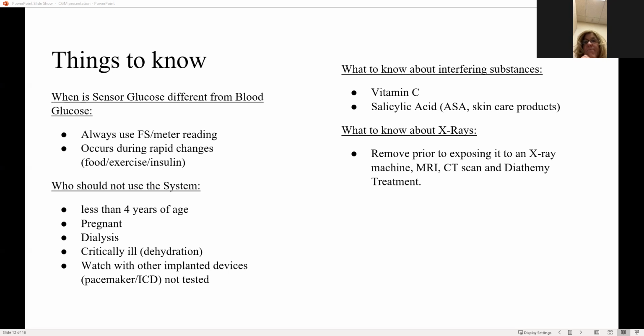X-rays, MRIs, CT scans, and diathermy, which is the use of heat. Any of those types of situations will likely ruin your Libre monitor, and it will not prove accurate after it's been scanned or has gone through any of these machines. So the recommendation is to remove it prior to having these tests done. Next slide.